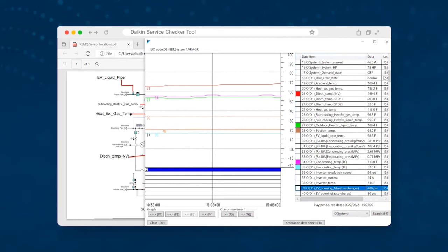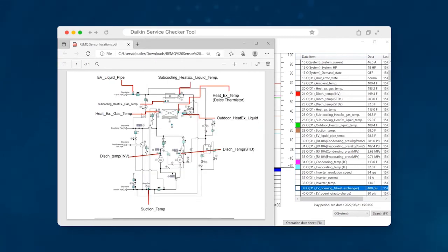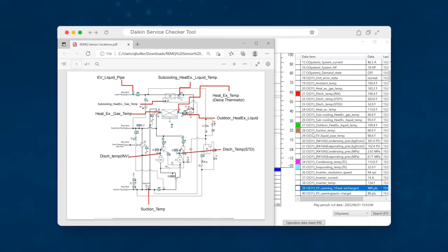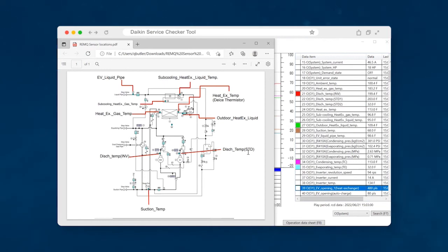I mean, anytime that I go on a system, no matter what the vintage is, even like VRV3, a system that I'm intimately familiar with, always pull up the piping diagram. And you're going to notice in the service manual that these values are not labeled the exact same way that they are here on the service checker. So I've gone through and made a little diagrams that actually match up and show what the naming is on the service checker versus... Just to keep the nomenclature straight.